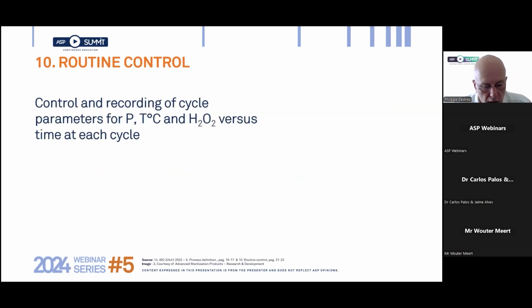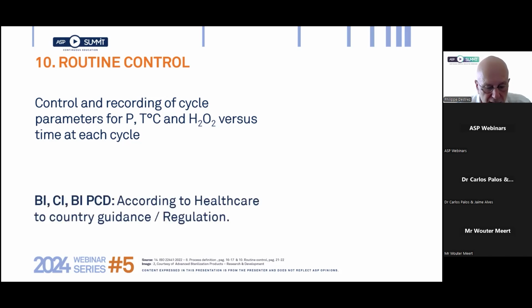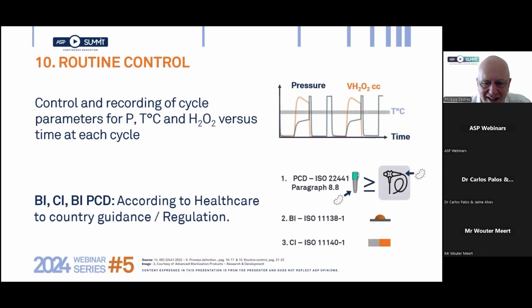So routine control includes the verifications to be performed periodically between validations, or operational control that needs to be performed at each cycle. The control and recording of process parameters are systematic. The use of BI, there should be pictures to illustrate this slide. Yeah, okay, here it is. The use of BIs, CIs or BI PCDs is according to the healthcare facility and applicable guidance or regulation.